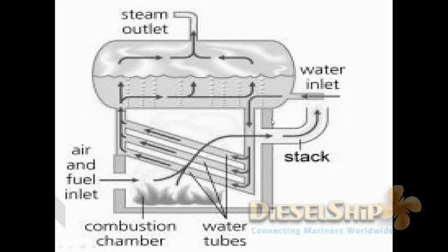So the previous design of the boiler had internal downcomers, with which the cold water after the feed water inlet enters the internal downcomer, and then as it gets heated up, its density decreases and thus forms steam, and then rises up the risers and gets collected in the steam space. Let's see another picture and understand the design concept and what the design changes are in the recent generation boiler.